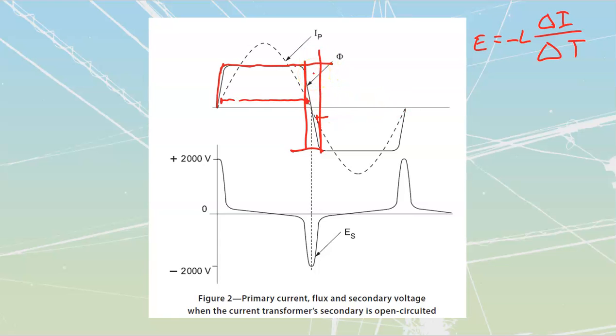And that's what they're showing us on the bottom. This rapid change in flux, during that change, all of a sudden we get this spike of voltage that comes out in the opposite direction, 2,000 volts, and then it flattens off at the top. As we reach saturation, my flux flattens off, the voltage flattens off. It's going to be low, and then all of a sudden, boom, it kicks out. You will see massive amounts of volts that can get kicked out.